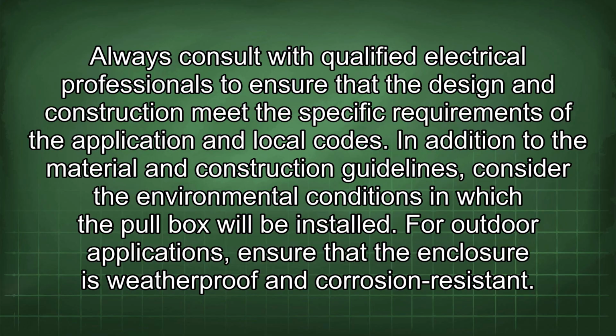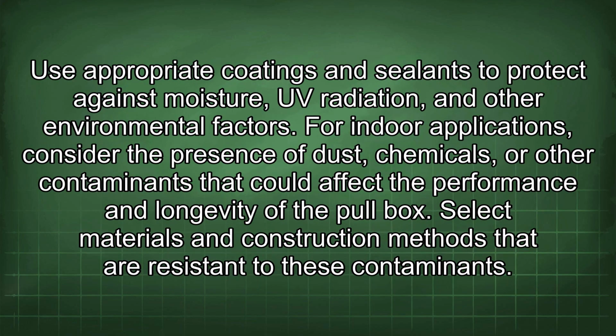In addition to the material and construction guidelines, consider the environmental conditions in which the pull box will be installed. For outdoor applications, ensure that the enclosure is weatherproof and corrosion resistant. Use appropriate coatings and sealants to protect against moisture, UV radiation, and other environmental factors. For indoor applications, consider the presence of dust, chemicals, or other contaminants that could affect the performance and longevity of the pull box. Select materials and construction methods that are resistant to these contaminants.